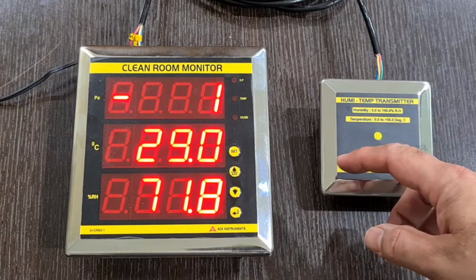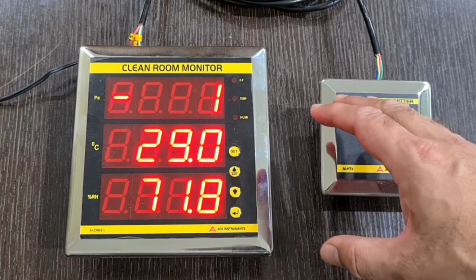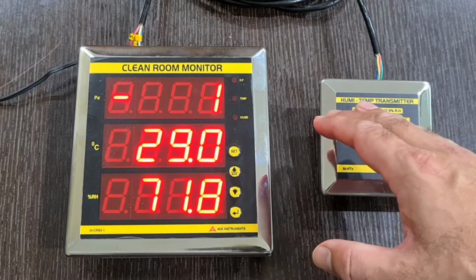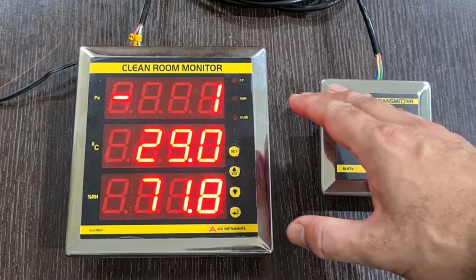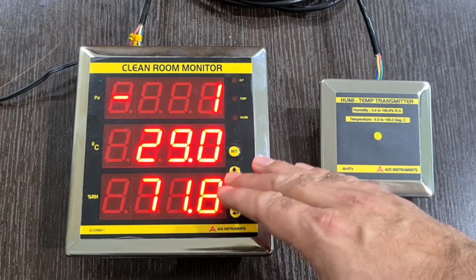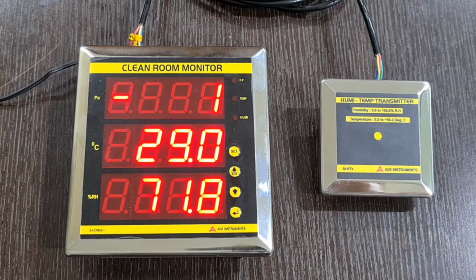The integrated buzzer alarm is programmable by user for any ranges, both low alarm and high alarm for each of the 3 parameters of temperature, humidity, and differential pressure, so that the user is alerted on field if the temperature or differential pressure or humidity readout is either lower than the desired readings or exceeds the desired limits. The buzzer alarm can be enabled or disabled as I just showed you.